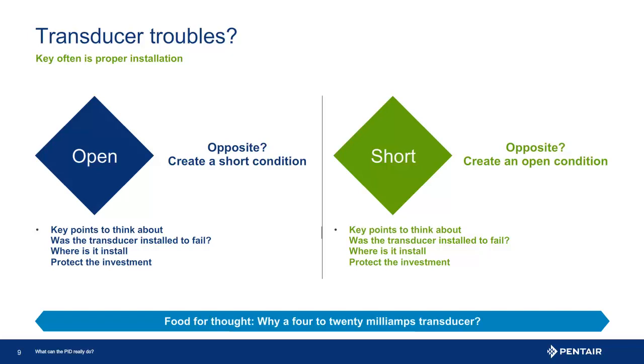Transducers can be quite simple to test. Think opposites. But before we get into the testing of a transducer, there are some common key points to consider. Was the transducer installed to fail? Who would do such a thing? Many people, unknowingly. An example is the use of nylon ties that can pinch and break the delicate wire. Or placement on a metal pipe that might pick up stray voltage. Or in a section of the system that has fittings too close to the transducer and creates water hammer.